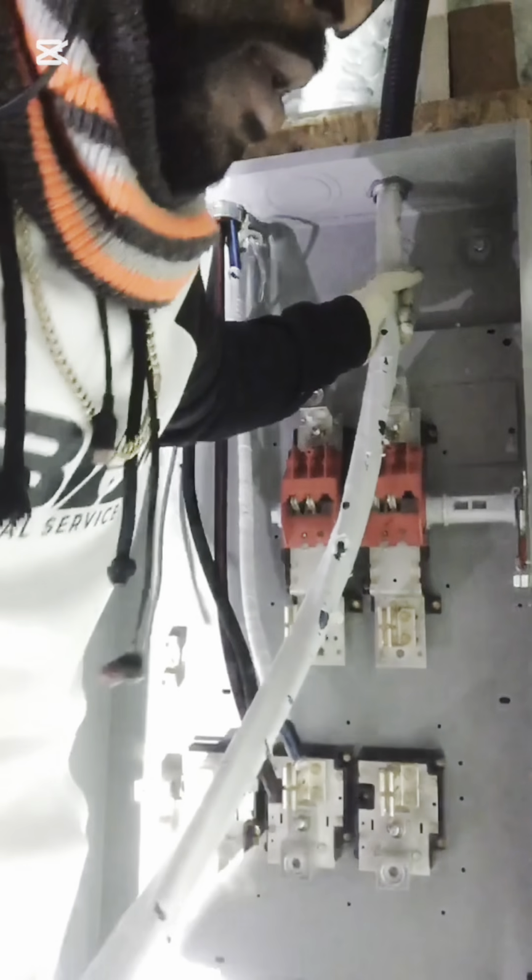As you can see, these cables are a different set of cables. They're TECK cable, we call it. And the only way to identify your TECK cable is by the stripes that they have. As you can see, they have red, blue, and just a plain black, and no white. So identifying your neutrals on a parallel path is very important. Also, making sure to use the proper connectors and bushings is also very important when it comes to the installation.